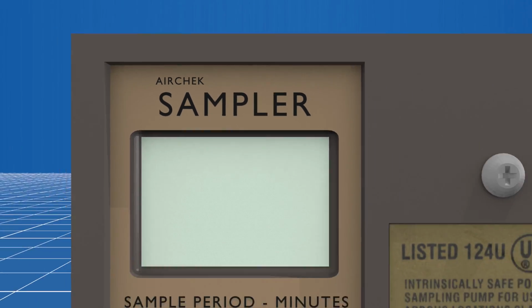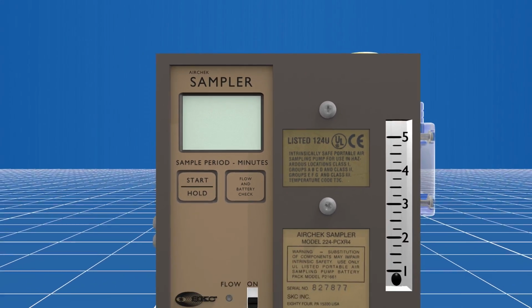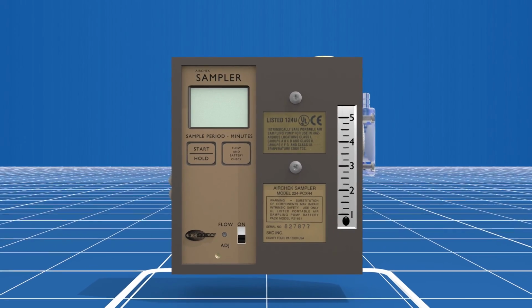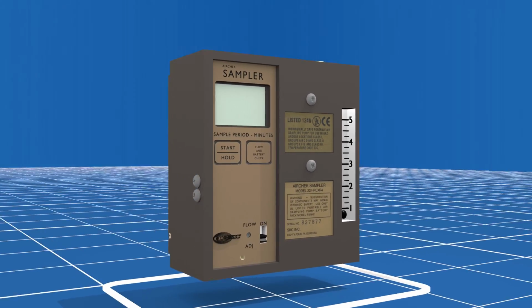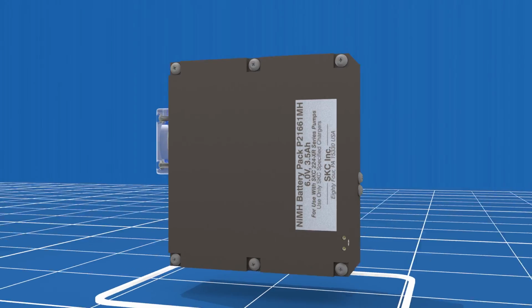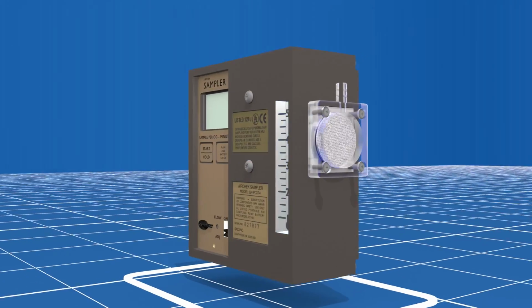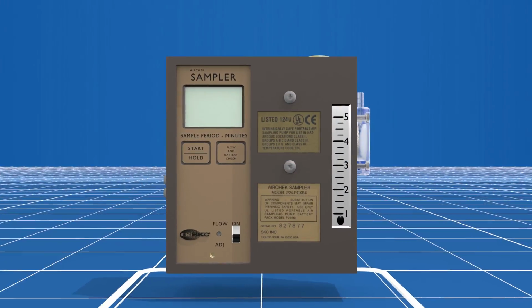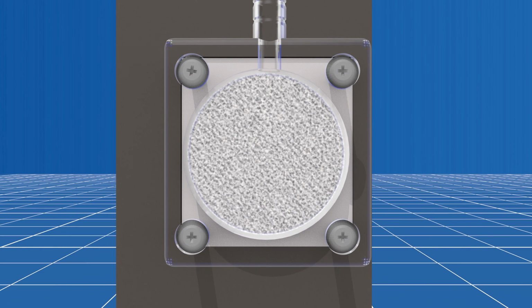Airchek Sampler SKC PCXR4 Basic Check. First, check the case. If it is damaged, please contact the IRSST. Next, check the inlet filter by looking through the housing.